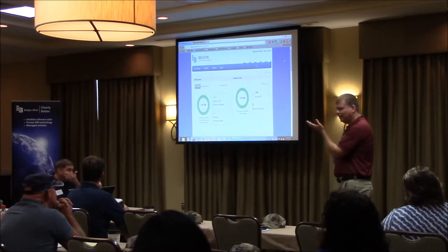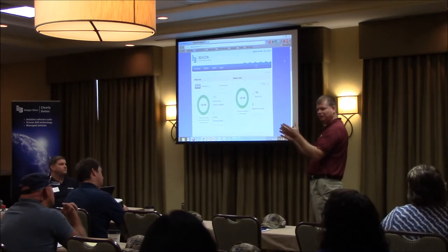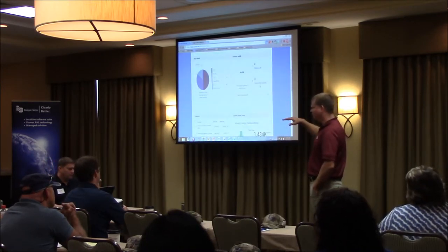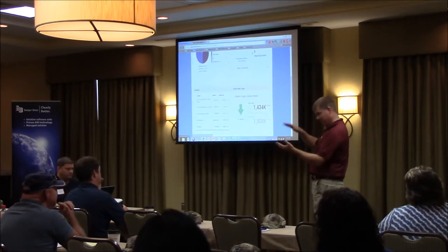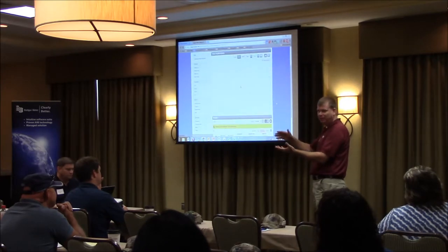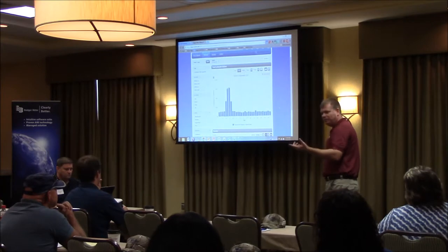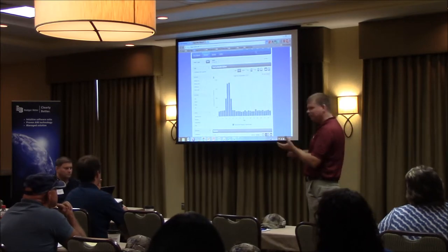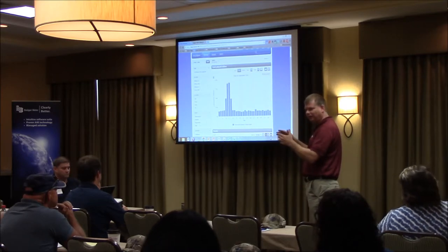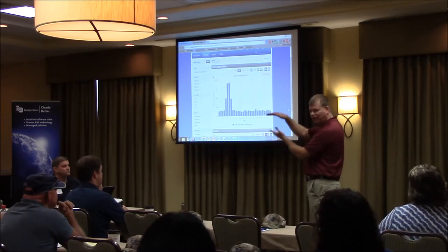One of the things there, they have a high non-revenue water amount, and they're trying to track that down. So when we're looking at their nighttime flows, is it 2,000 gallons an hour or is it 3,000 gallons an hour? Well, it's somewhere in between there. Is it 2,900 or 2,100? That's a big difference at that point. And Rural Water's helped them on some leak detection. We're working with them trying to get that down. And we're finding some leaks and repairing some leaks on their behalf, but is it making a difference? It's kind of hard to tell when you've got such a big step.